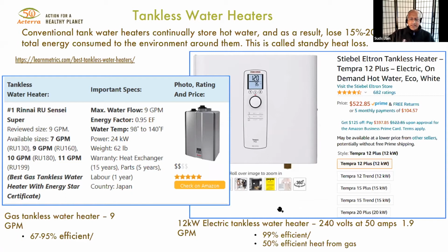The problem with these is that a 12 kilowatt electric tankless water heater runs on 240 volts at 50 amps. A lot of people only have 100 amp service coming into their house, so this consumes half the energy for your house. And they only do 1.9 gallons per minute, so two people couldn't comfortably shower at the same time with these. Whereas at 9 gallons per minute, 3 or 4 people can shower at the same time.